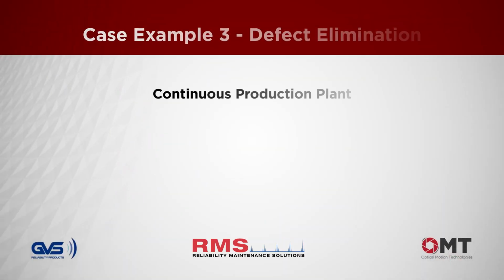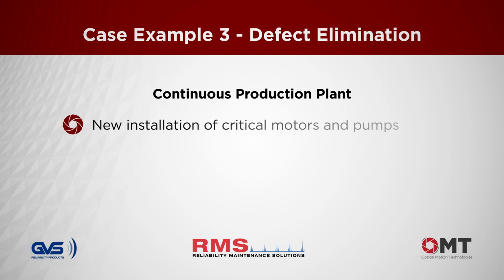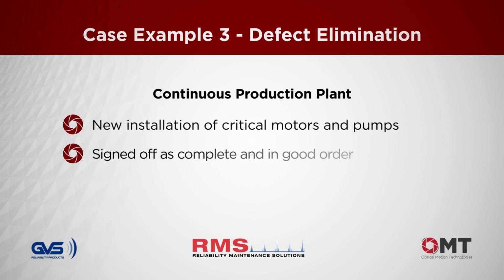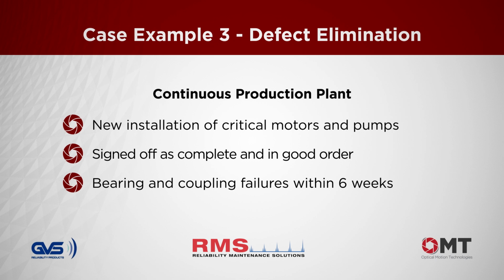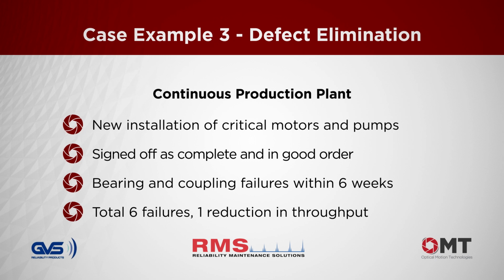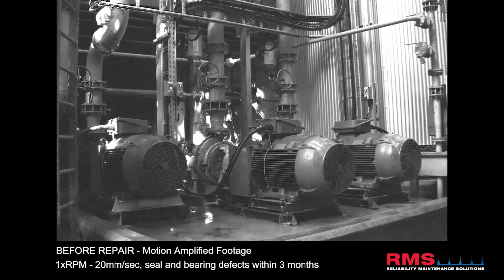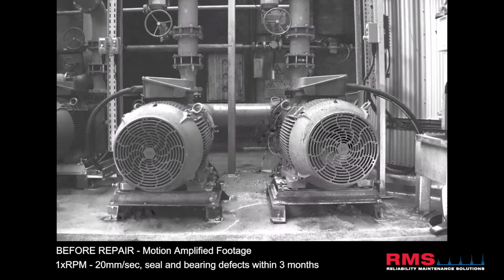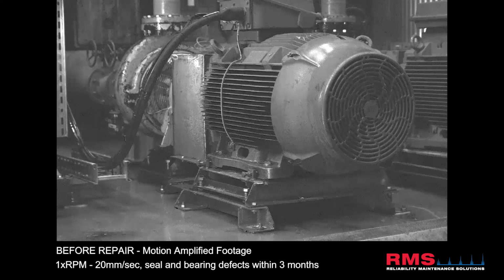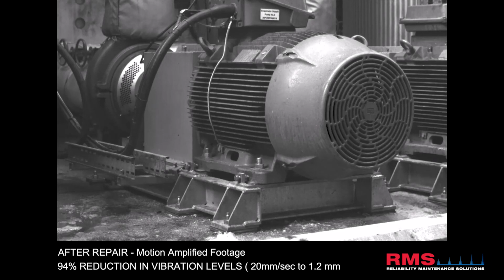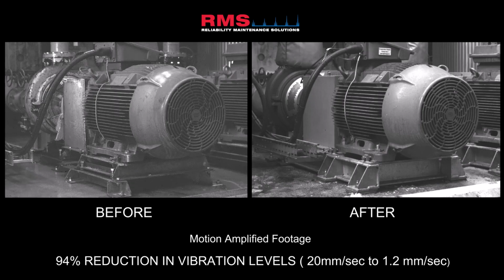At a continuous production plant, a new installation of critical motors and pumps was signed off from the projects team to operating team as complete and in good order, ready to use in the process. However, bearing and coupling failures were occurring within 6 weeks of installation and continued for 12 months of operation, resulting in 6 failures and 1 incident of reduced plant throughput. Motion Amplification was deployed to review the machines and found the root cause of the issue within 15 minutes. The bases were poorly installed and of insufficient design quality. All 3 motors and pumps needed to come offline, be removed, and have the defective bases remanufactured to ensure lower vibration levels and reliable continued operation.